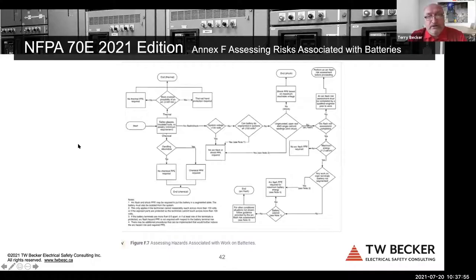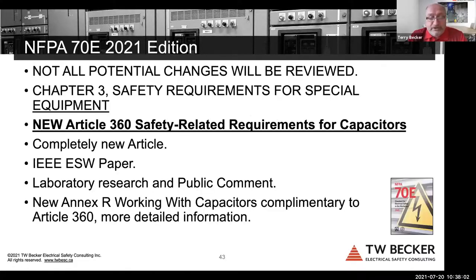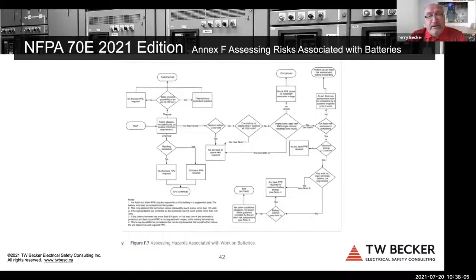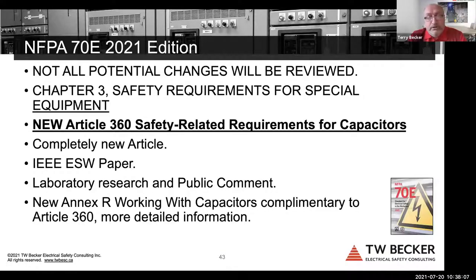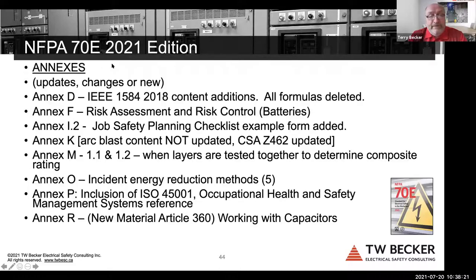And again, I think we're going to see a lot more of this come with large storage battery systems going in, but even UPS battery systems. This was actually in the handbook for 70E and probably pulled from the handbook and brought forward into the annex of 70E. So again, the capacitor annex has significant information. I encourage you, if you don't have a copy of 70E, the new edition, buy it just for this annex. And again, the annexes were cleaned up in 70E. We do have some divergence and some new annexes in Z462. So I'm going to accelerate here a little bit.